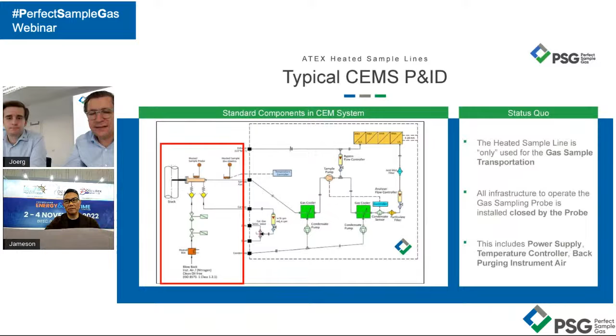And this is, let's say, the innovation of our concept. So far, all of this is installed close by the probe. Maybe also there, Jameson, you have a long experience of many probe installations, and you know how difficult sometimes the areas are where the probe installation has to take place. Our concept with the hybrid heated line is the following: we will bring the entire, let's say, supply which is needed to operate the probe within one heated line, within one bundle.